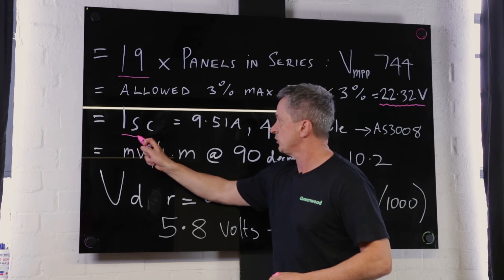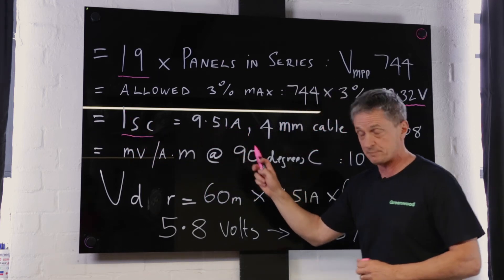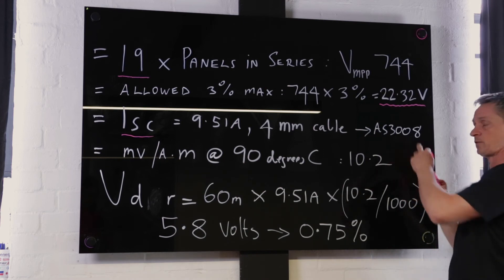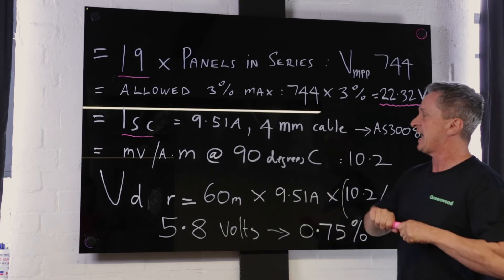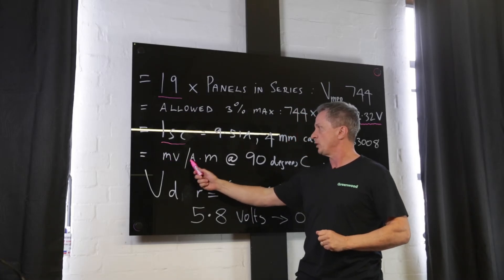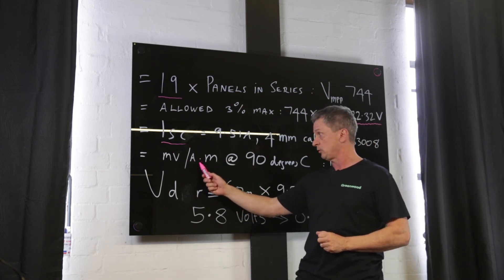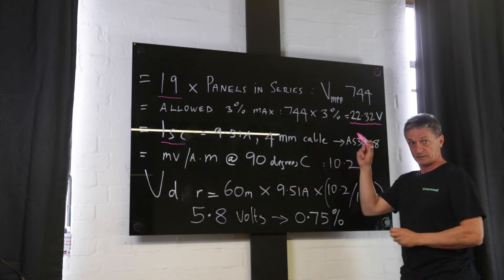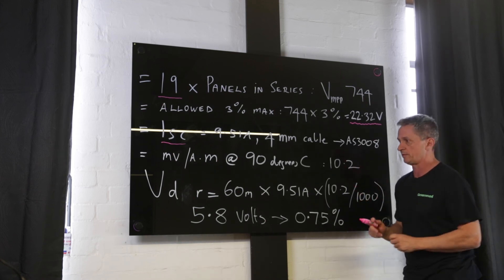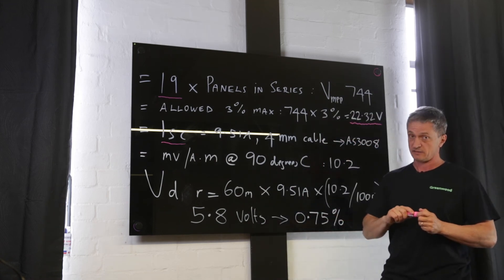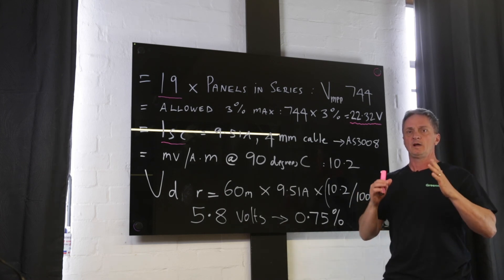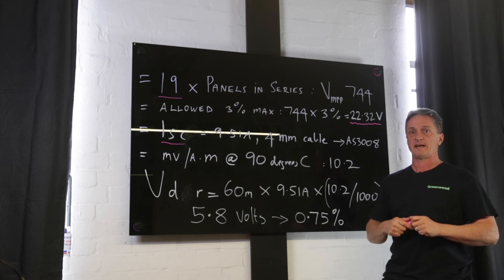The panel we're using has a short circuit current of 9.51 amps. We've selected 4mm cable and go to AS3008. We look at the millivolt per amp metre rating — for every one amp through the cable for one metre, what is the drop in millivolts at 90 degrees? For this 4mm cable it is 10.2 — a very important figure. There are other calculation methods, such as using the resistivity of copper, so please check your results with online calculators as they can really vary.